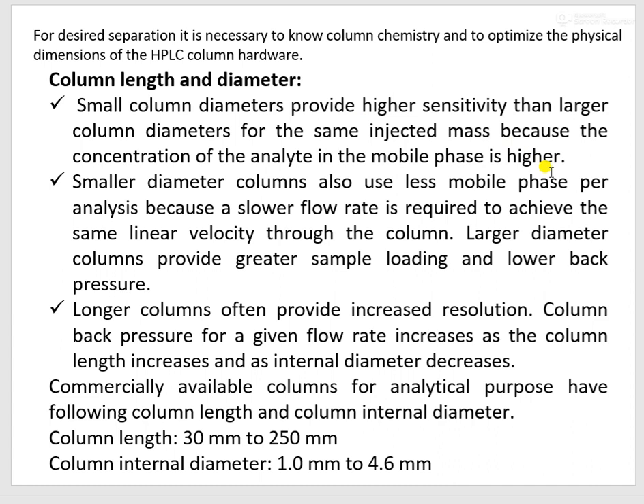With a small diameter column compared to a larger diameter column, the sensitivity obtained with a small diameter column is very high, because in a small diameter column, less volume of mobile phase is used, and because of that, the injected sample will not be as diluted as in a large column diameter where the volume of mobile phase is more. Hence, you will get good sensitivity with a small diameter column. Small diameter columns also use less mobile phase per analysis because a slower flow rate is required to achieve the same linear velocity through the column.